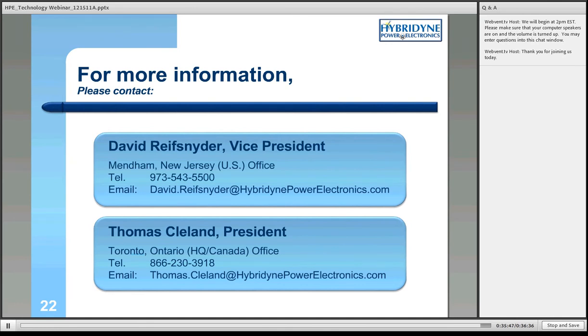So if that's been done, you may not be as optimally configured as you'd like to be when taking advantage of a hyperwatt inverter, because you would effectively say, well, I don't want to over panel as much, because if I shed power at the high end, I'm throwing it away because I am going to get it at the low end. I don't need to jigger the panel strings to try to increase my ability to derive power. I'm doing it by having the deeper, lower threshold. But yeah, it's a very good approach to plug in a hyperwatt inverter to replace a failed conventional inverter.